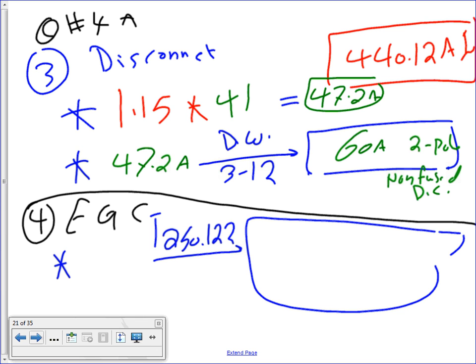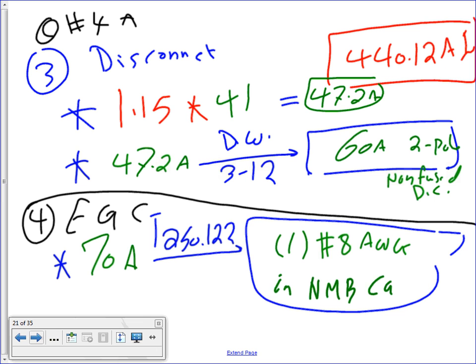Why two-pole? Why non-fused? Did this say anything about fuse? We already sized the circuit breaker. We don't need a fuse. The last thing is a piece of cake, guys. The equipment grounding conductor. You take the 70 amp overcurrent protection device to 250.122. That will get you a healthy number 8 AWG in NM-B cable. Right?